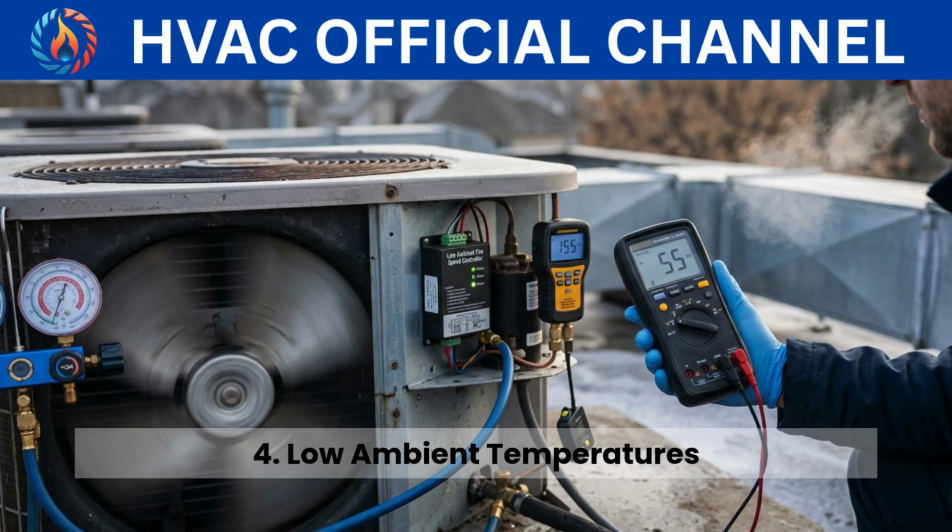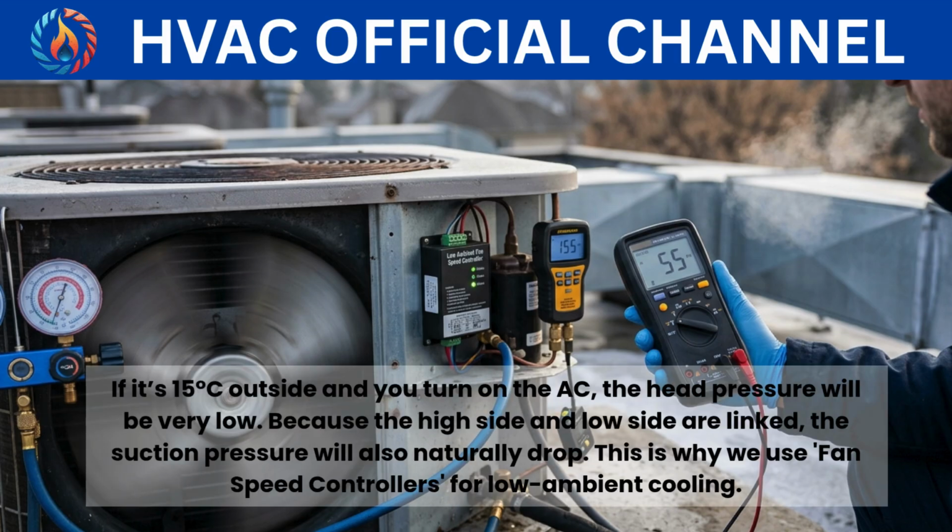4. Low ambient temperatures. If it's 15 degrees Celsius outside and you turn on the AC, the head pressure will be very low. Because the high side and low side are linked, the suction pressure will also naturally drop. This is why we use fan speed controllers for low ambient cooling.